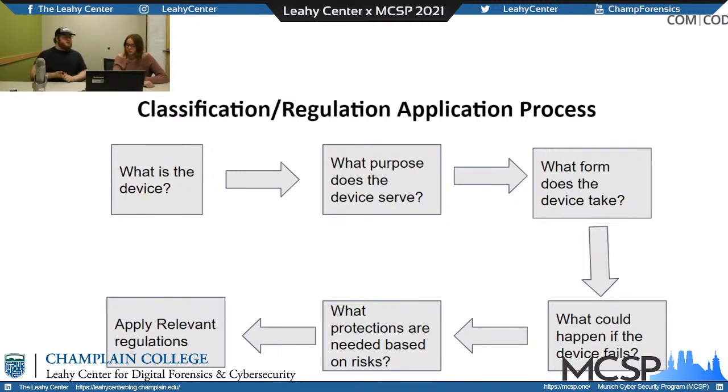Having a third party monitor it. Some hospitals do monitor pacemakers while they're in the patients, to make sure that they're secure. But you can't cover them all. So this is where you have to apply these regulations and then figure out what they have for afterwards. Both the EU and US have frameworks that you need to have in place for your post-market introduction. So you need to monitor the landscape.